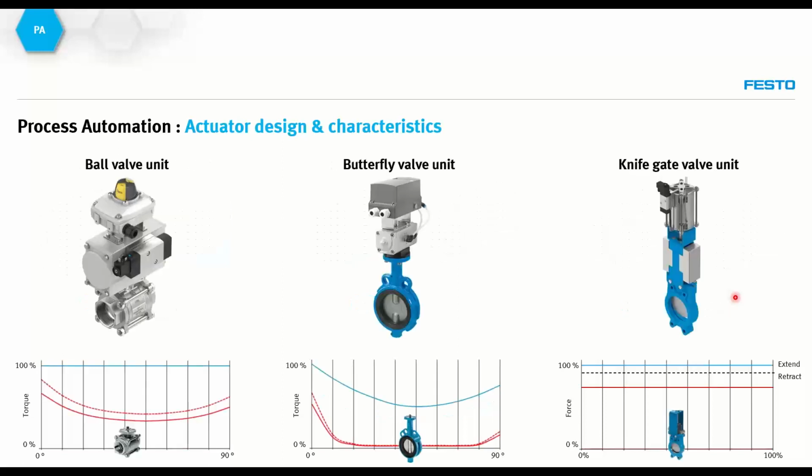Now, if we look at those charts or graphs, we use those graphs for both process valves and the actuator to show the relation between selecting the right actuator for the right process valve. In this graph, we see the torque curves of the ball valve, also including the safety factor of the torque requirements. We will come to know the recommendations for these safety factors and what we can take into consideration.